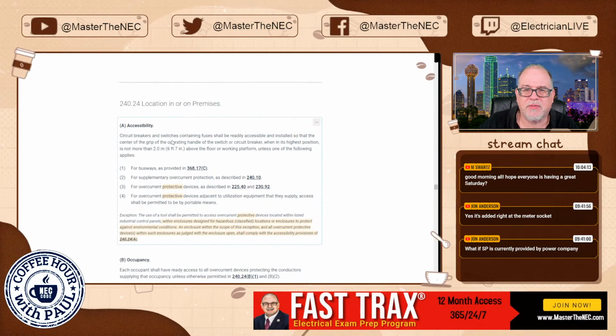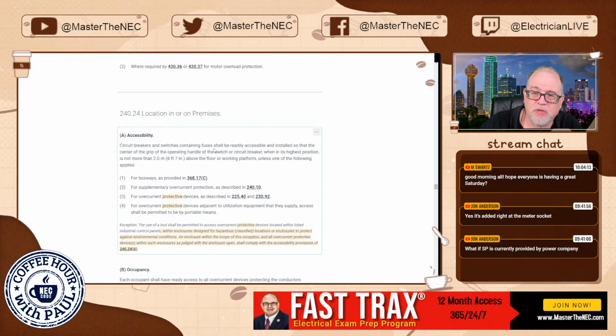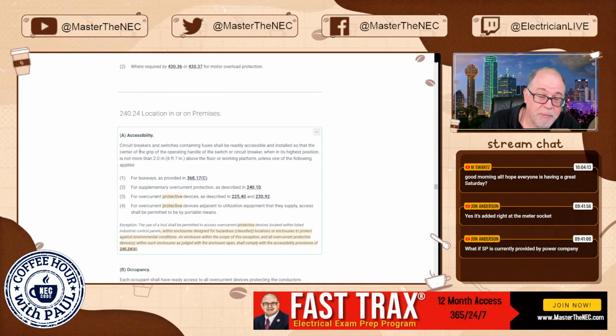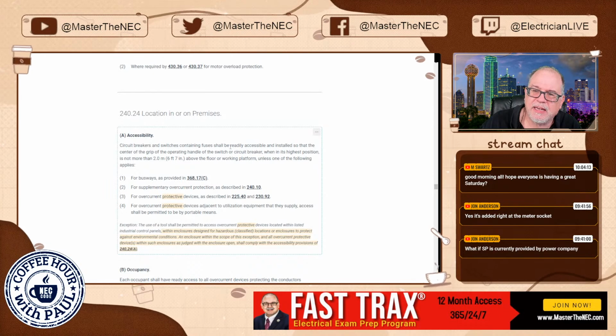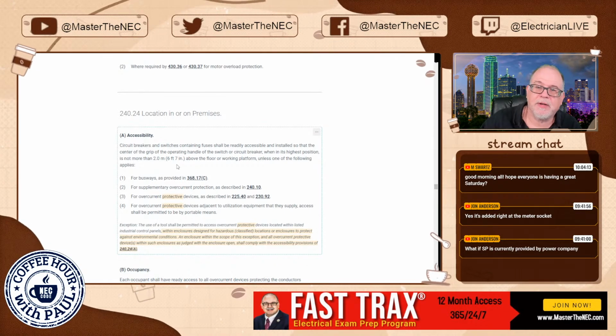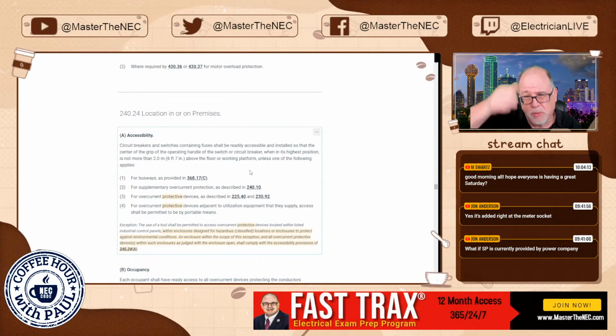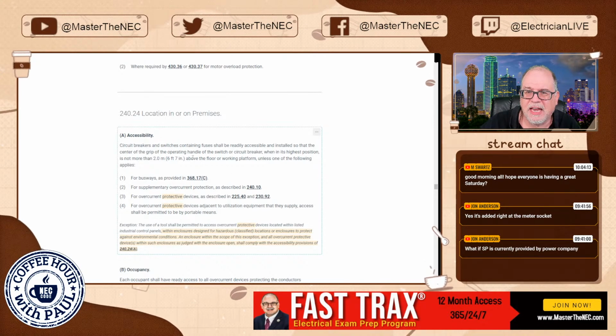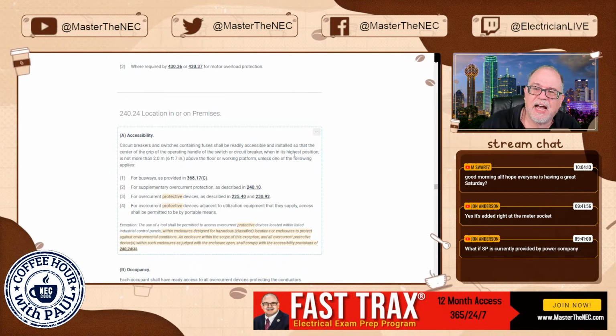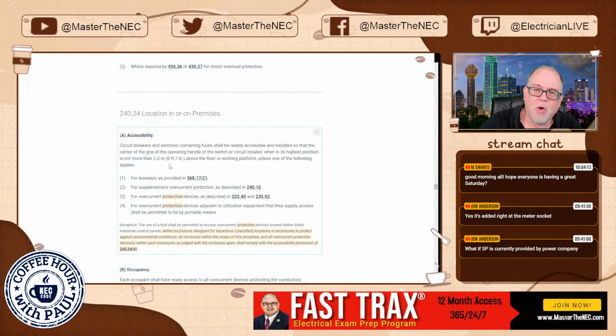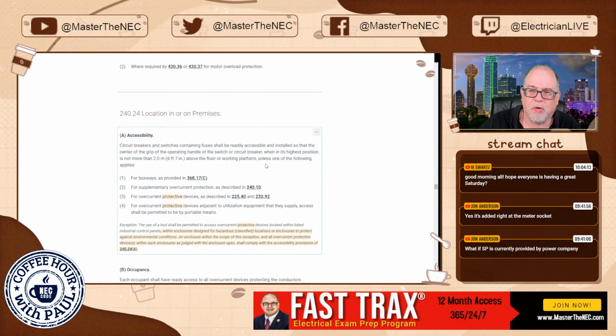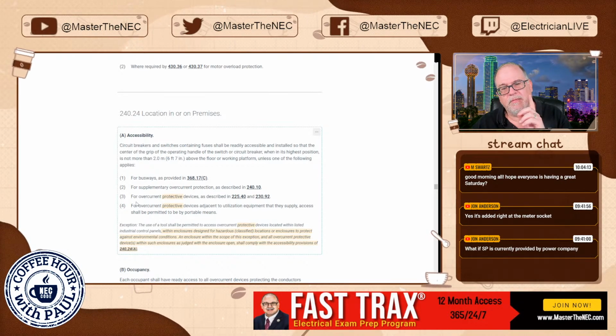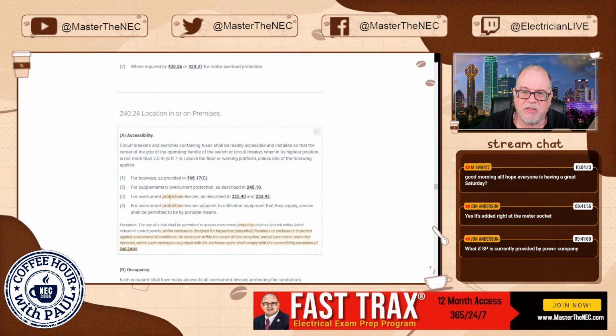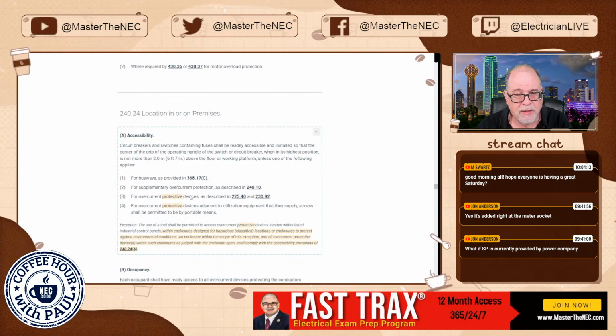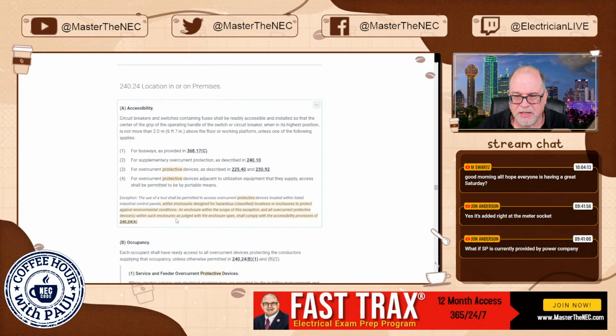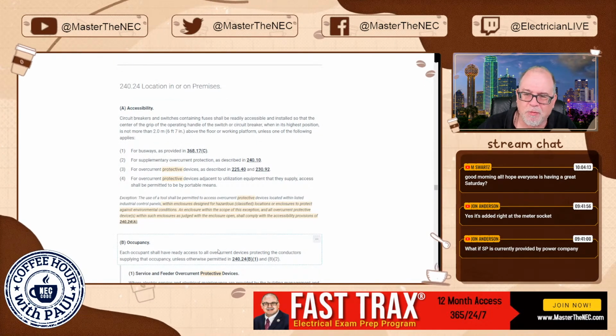240.24, location in or on the premises. All right, so circuit breakers and switches that contain fuses shall be readily accessible and installed so that the center of the grip of the operating handle of the switch or the circuit breaker, when it is in its highest position, in the on, up position, is not more than 6 feet 7 inches above the floor or working platform, unless one of the following applies. All right. So they've added "overcurrent protective devices" here. They added the word "protective devices." That's what we're talking about, right? Because we are in 240. So they simply added that there, and you have some exceptions down here in the rules. To me, not overly significant, but we'll read it.